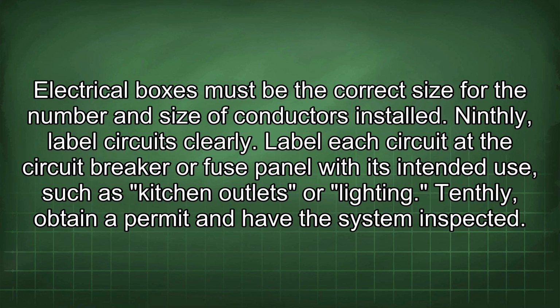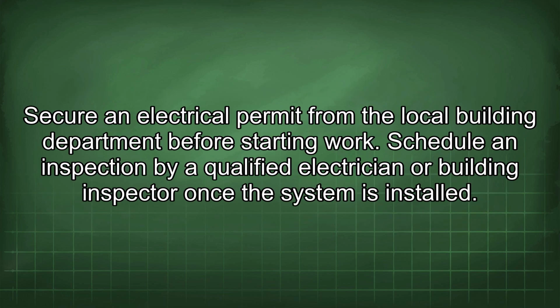Ninthly, label circuits clearly. Label each circuit at the circuit breaker or fuse panel with its intended use, such as kitchen outlets or lighting. Tenthly, obtain a permit and have the system inspected. Secure an electrical permit from the local building department before starting work. Schedule an inspection by a qualified electrician or building inspector once the system is installed.